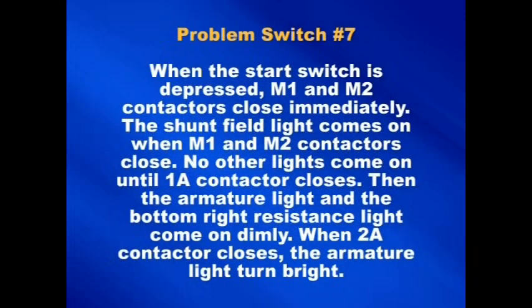Should the apprentice electrician draw problem card number 7, this is what he'd have. When the start switch is depressed, M1 and M2 contactors close immediately. The shunt field light comes on when M1 and M2 contactors close. No other light comes on until 1A contactor closes. Then the armature light and the bottom right resistance light come on dimly. When 2A contactor closes, the armature light turns bright.